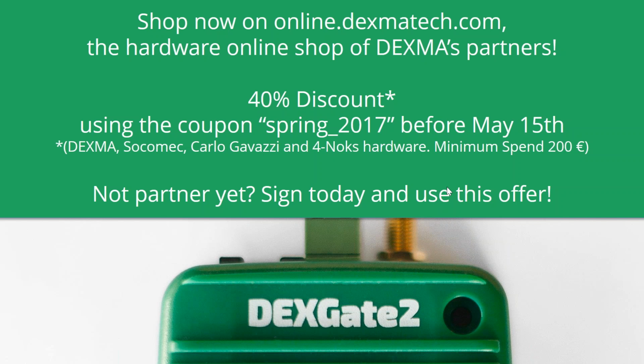Of course, if you want to have fewer problems, think that if you lose internet, for example, you will lose the communication to that net. So think of Modbus TCP, that's something that is very useful, but having one gateway in a city and from there reading all the world is difficult, and if you lose the internet, for example, in one of your buildings, you will lose all the information. So it's recommended to install close gateways, but it is possible, of course.